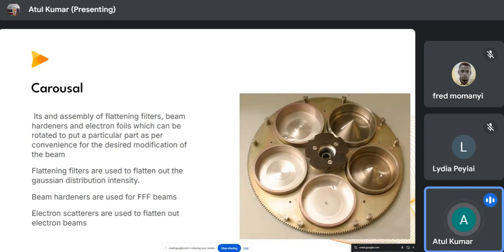This one is the flattening filter free beam, and this one is an electron scatterer. If you need an electron scatterer, you will make your electron fall in this electron scatterer. If you have an X-ray coming out from that slit, you can make that X-ray fall in this flattening filter. What it does is flatten your beam, because the intensity at the center is higher as compared to the intensity around it.